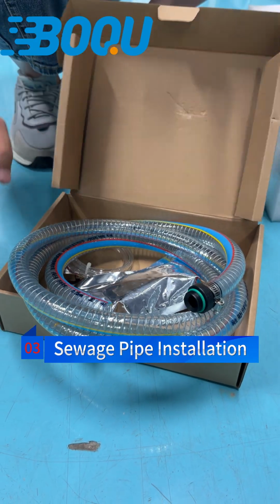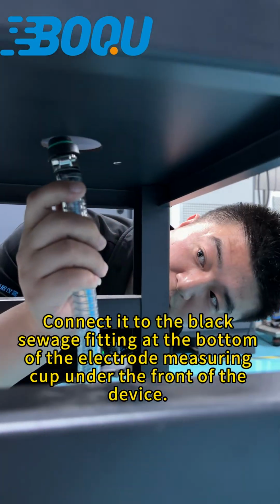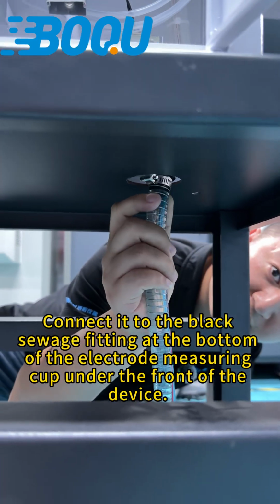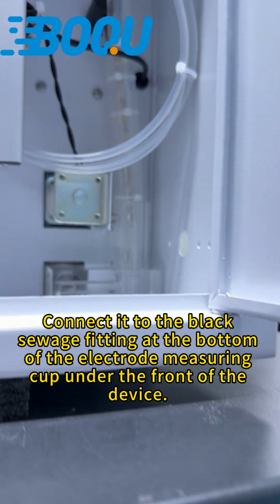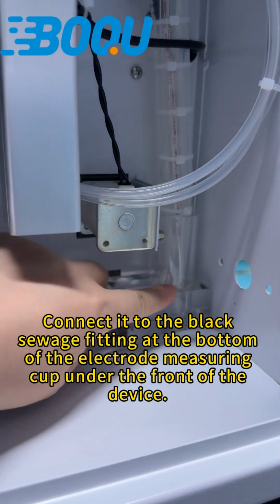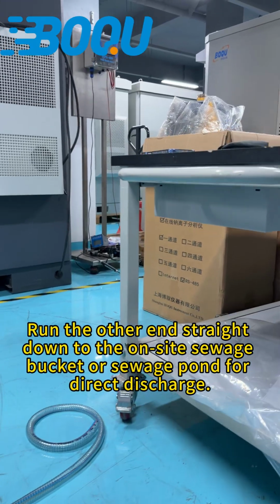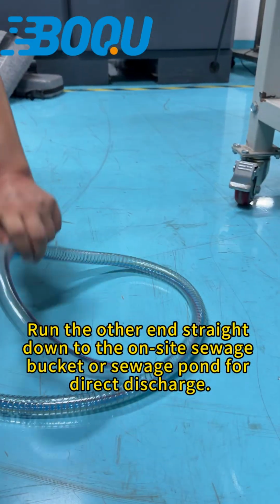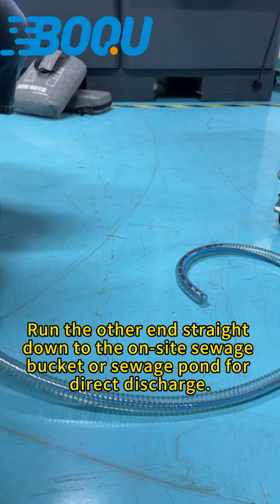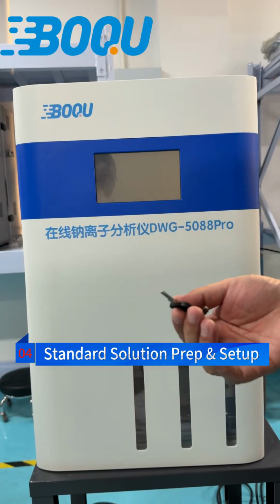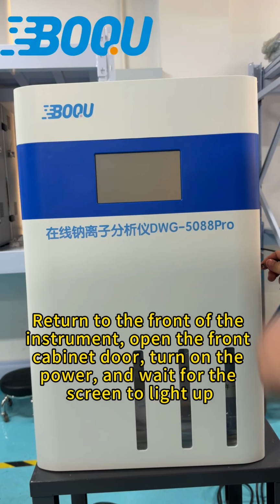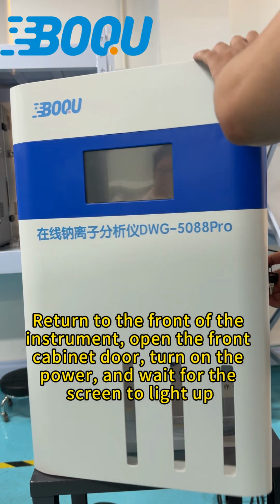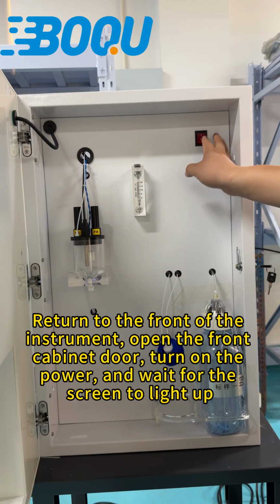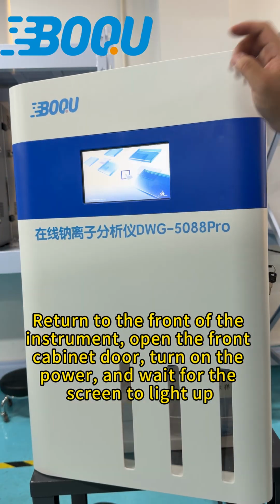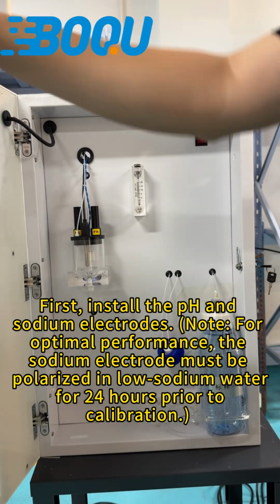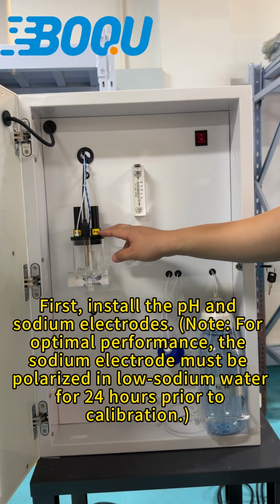Sewage pipe installation. Take out the sewage pipe. Connect it to the black sewage fitting at the bottom of the electrode measuring cup under the front of the device. Run the other end straight down to the on-site sewage bucket or sewage pond for direct discharge. Standard solution prep and set up. Return to the front of the instrument, open the front cabinet door, turn on the power, and wait for the screen to light up. First, install the pH and sodium electrodes.